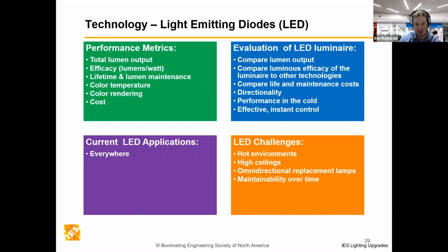Maintainability over time is a big one because a lot of, especially earlier LEDs, didn't have replacement parts or weren't really replaceable. So having replaceable drivers, lenses, and that sort of thing over time is something owners will want to care about. Make sure the fixtures you're specifying have these things and can replace the drivers separately from the rest of the fixture, so you're not just trashing a whole fixture when it comes time to replace the LED.